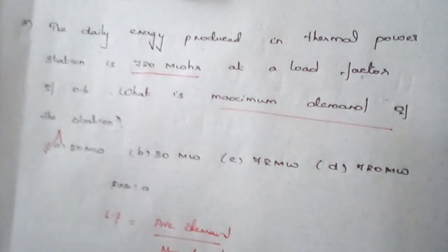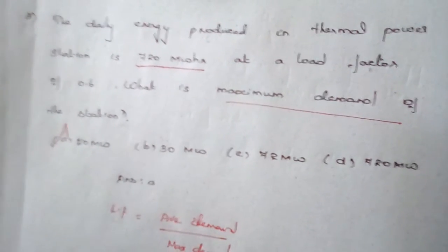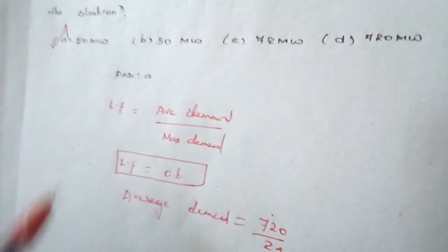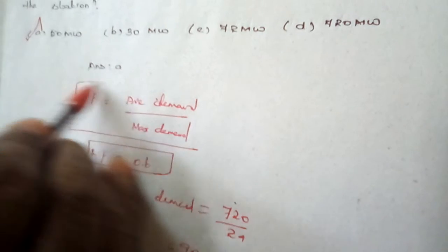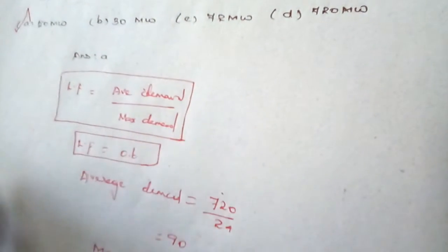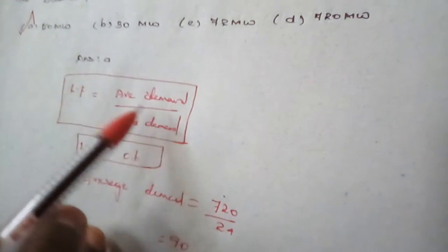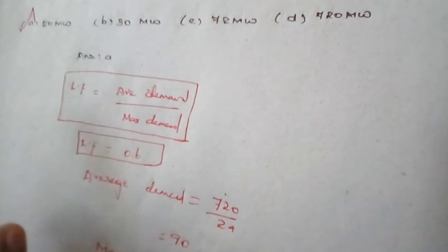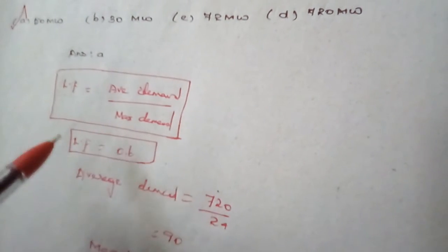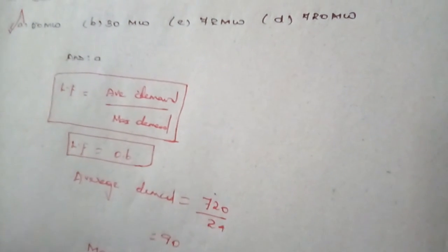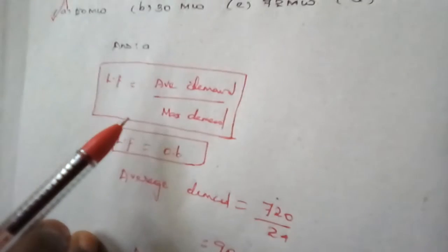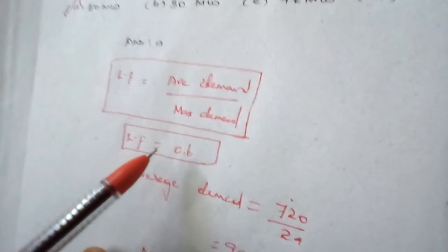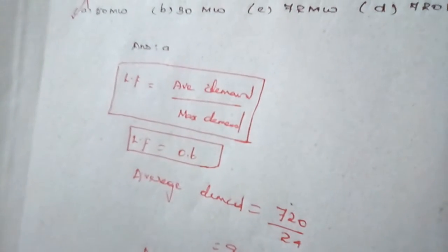This formula is very important for finding maximum demand or average demand once the load factor is known. The key formula is: load factor equals average demand divided by maximum demand. Knowing this, we can find any one of these three quantities given the other two.